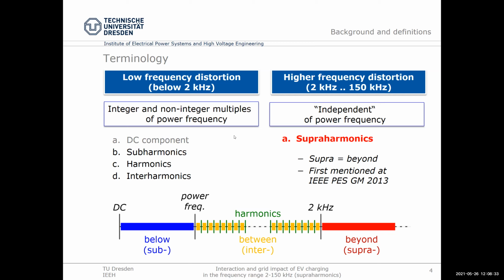And regarding the terminology, there is no real established terminology yet because this phenomenon is rather new. But often it is called supraharmonics, supra coming from a consequent continuation of the terminology below 2 kilohertz, because supra means beyond, and this is just the frequency range beyond the harmonics. It was first introduced at the IEEE PES general meeting in 2013, and it is more and more common to use this term, even if it is still sometimes under discussion.